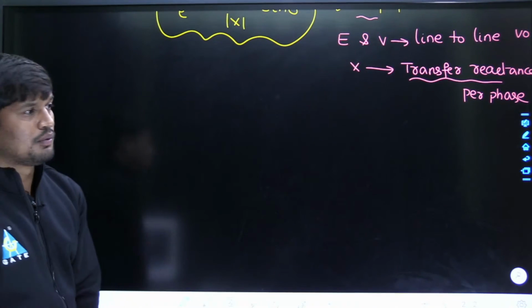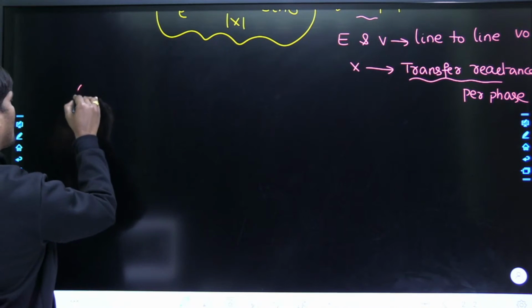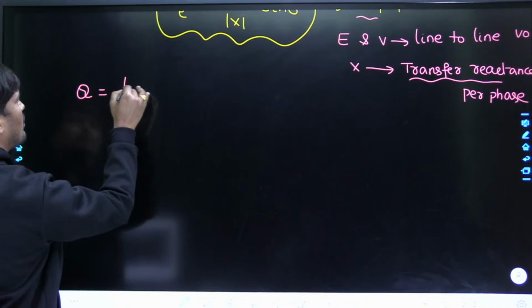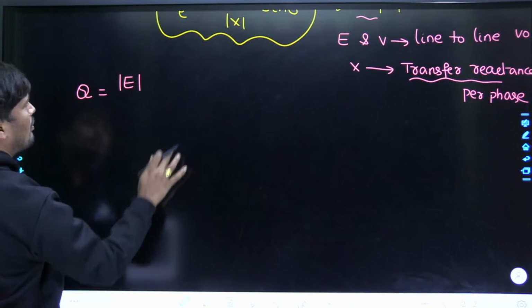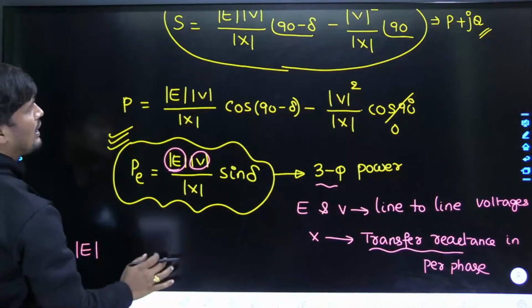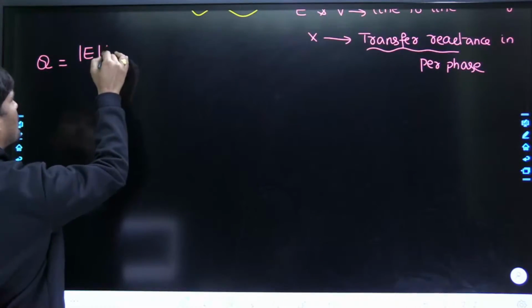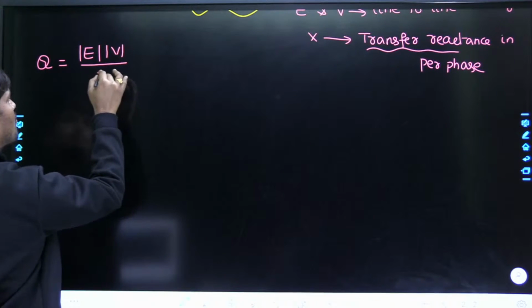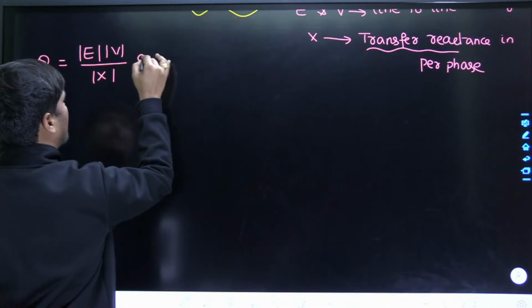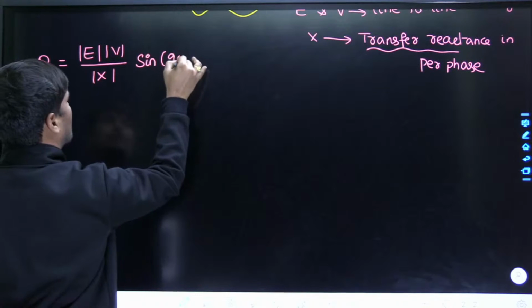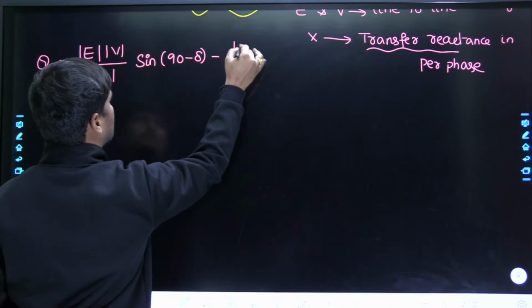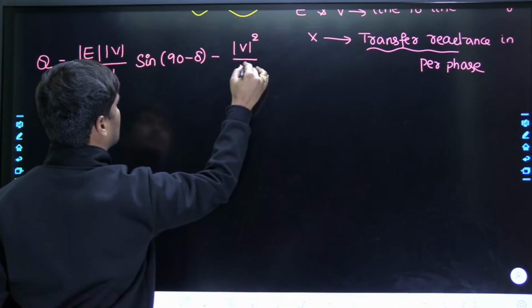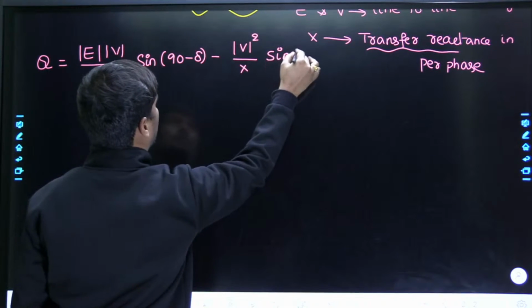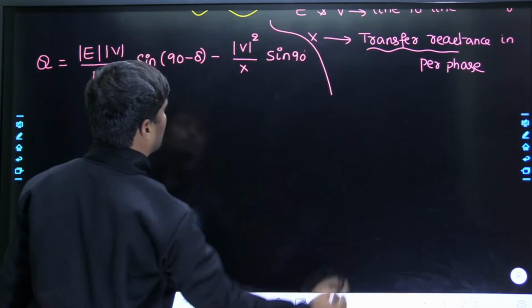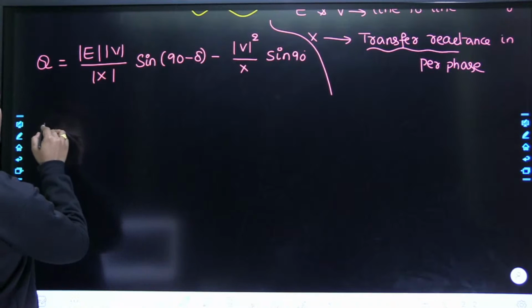Let us move forward. Reactive power Q is obtained by multiplying the total power equation appropriately. So reactive power Q equals E into V divided by X, sin(90 minus delta), minus V squared by X sin 90. This is the reactive power equation, or wattless power.